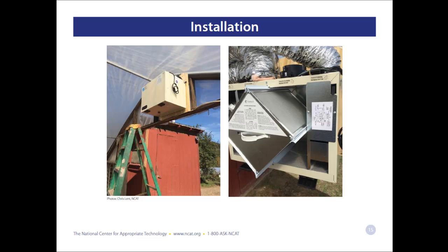And once the ventilation unit is in place and the vent hoods are in place, you can then start running the ductwork. So that's what you see in this second photo here in this slide, the ductwork is coming off the top of the intake and output portals on top of the heat recovery ventilator and running to the respective vent hoods. And you see in the middle of that picture is the heat exchanger cube. That's the aluminum heat exchanger that the air gets transferred through in order to transfer the heat from the warm inside air to the cool outside air as it's being drawn in.